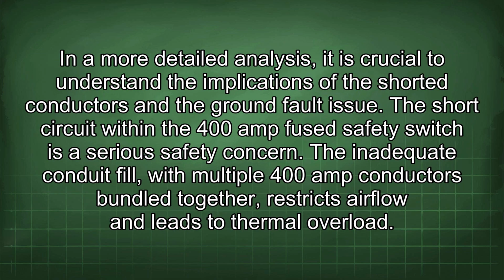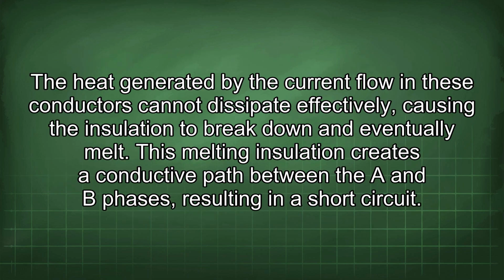In a more detailed analysis, it is crucial to understand the implications of the shorted conductors and the ground fault issue. The short circuit within the 400 amp fused safety switch is a serious safety concern. The inadequate conduit fill, with multiple 400 amp conductors bundled together, restricts airflow and leads to thermal overload. The heat generated by the current flow in these conductors cannot dissipate effectively, causing the insulation to break down and eventually melt. This melting insulation creates a conductive path between the A and B phases, resulting in a short circuit.